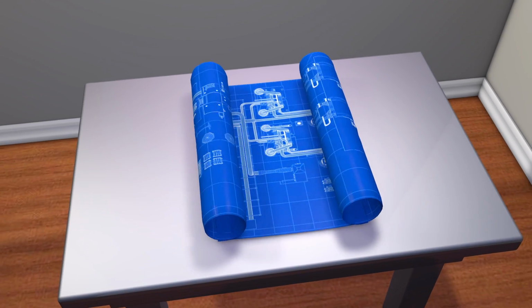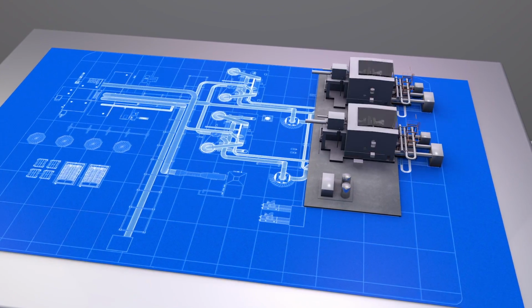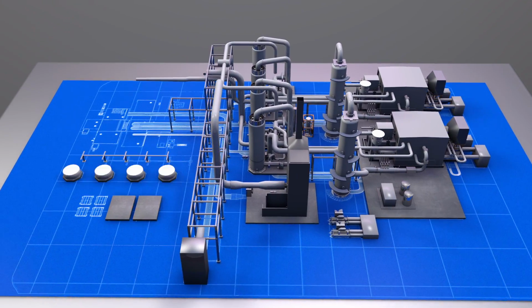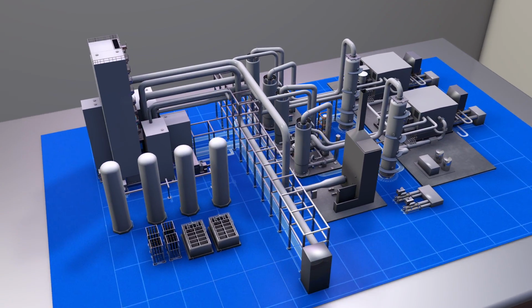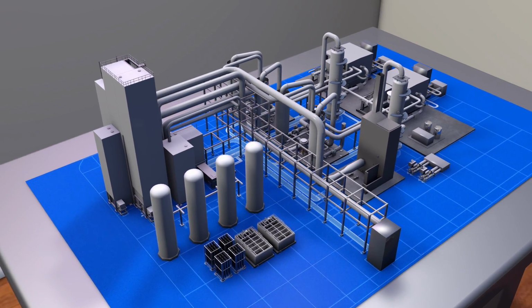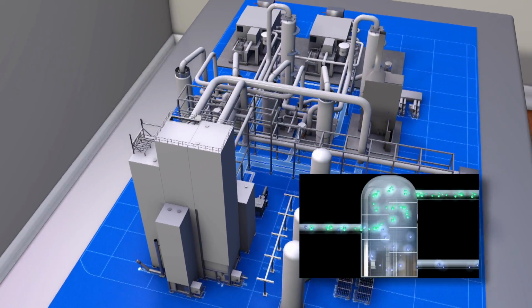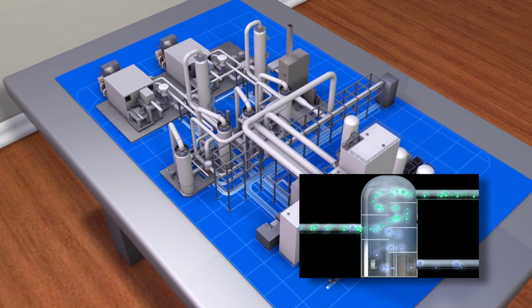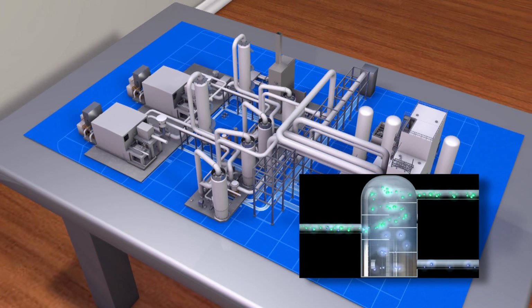This energy is produced in a process called oxy-fuel combustion, in which fuel is combusted in a pure oxygen environment. The continuous supply of oxygen requires an air separation unit, which separates air into its constituent parts at high purity. Here, the air is cooled to very low temperatures, liquefied, and physically separated in a cryogenic distillation process. Separating out the nitrogen before the combustion process avoids the formation of nitrogen oxides, or NOx, during combustion. Nitrogen oxides are difficult to eliminate air pollutants, typically tied to power production.